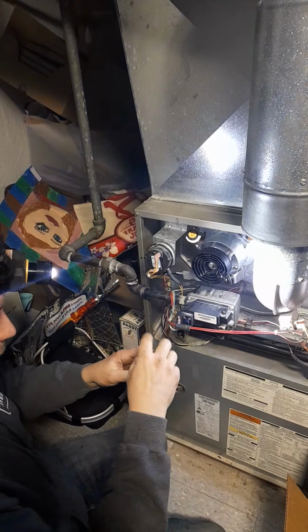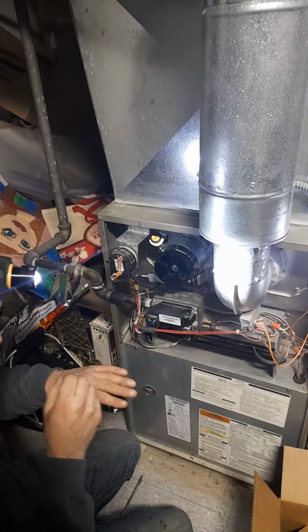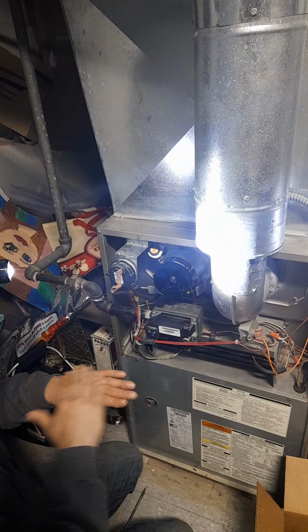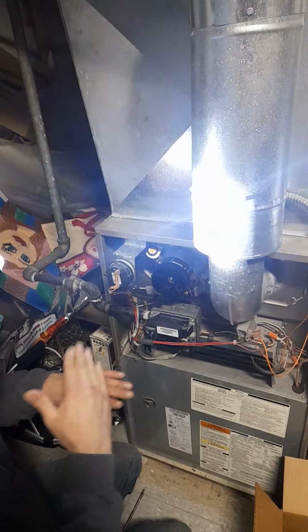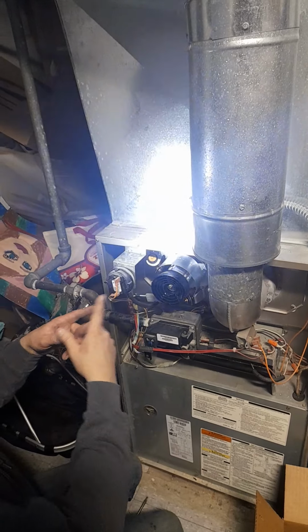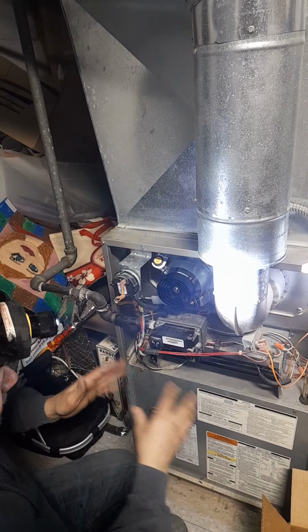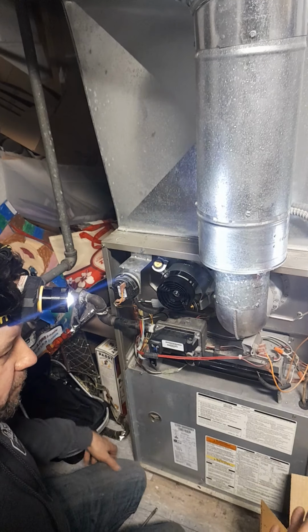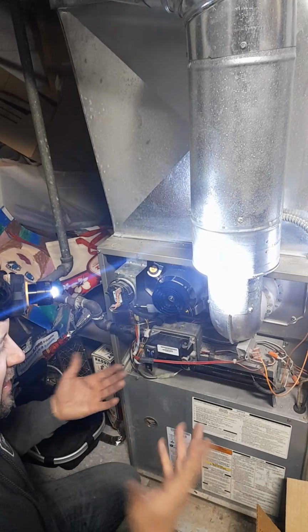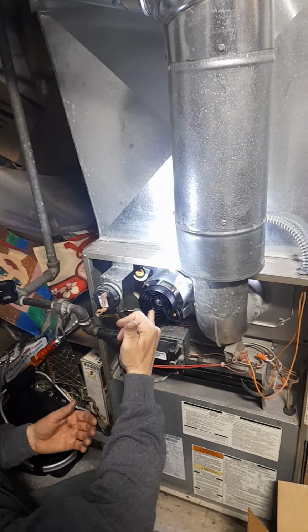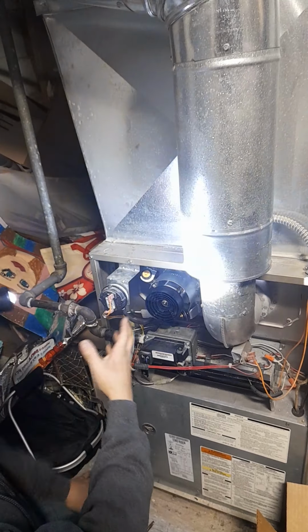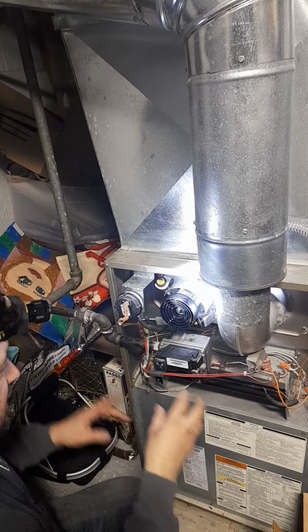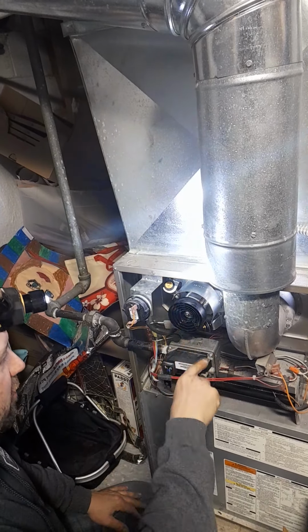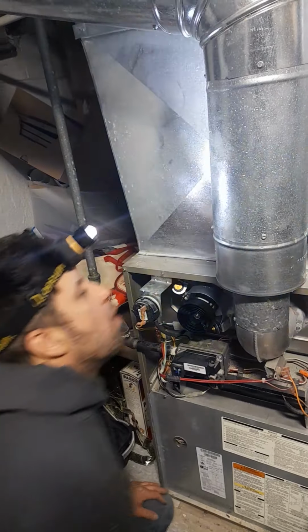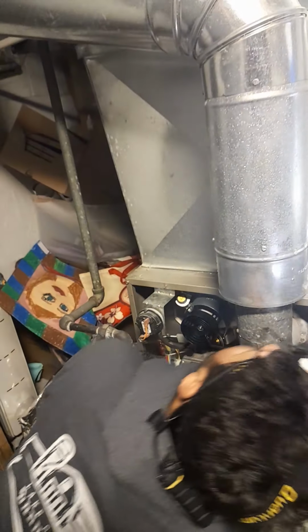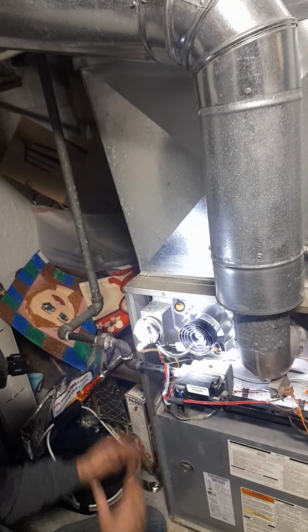And this thing just makes sure that it gets over a threshold of 0.27 inches of water column. So if you had a straw in water and you lifted 0.27 inches above the meniscus of the water level in the glass, that's 0.27 inches of water column. And you need more than that to actually close the switch to verify that this heat exchanger integrity is acceptable, that it's still there. Otherwise, it's kind of an unsafe condition. Second, if this would have failed, then you obviously can't get the switch to close, and you're not sucking out the fumes. So this is like a negative pressure to make sure that stuff gets pushed up the chimney, you know. And that's that. So that just verifies.